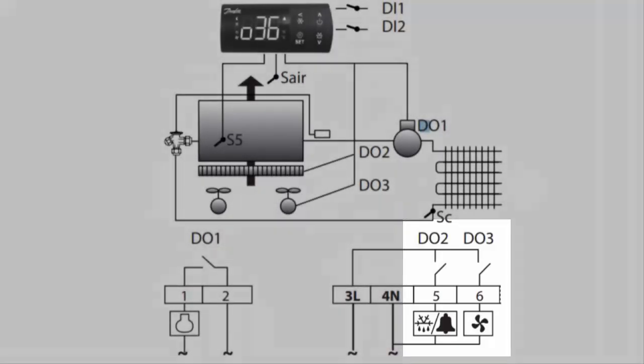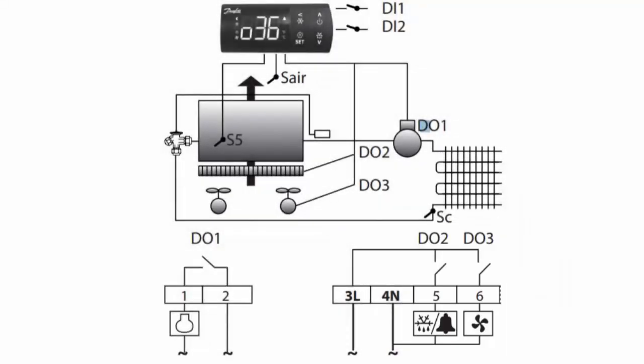Another example of dry contacts would be the contacts in a typical relay like a 9340 or a compressor contactor. You have to feed power in for current to go out. It doesn't grab current from some other point powering the device itself, like in this case here.